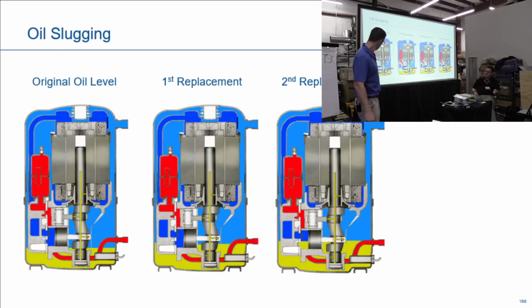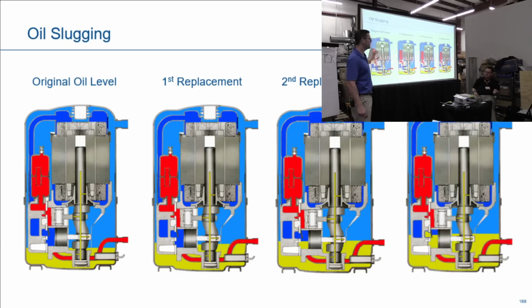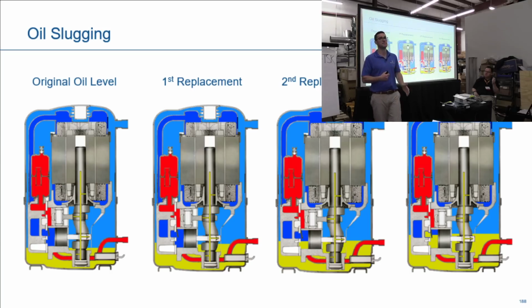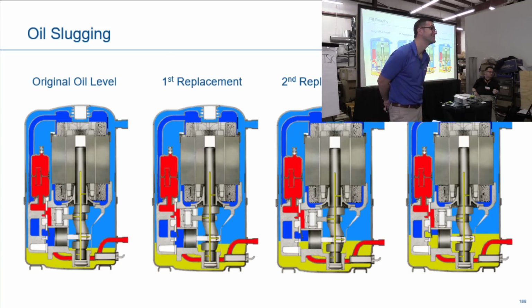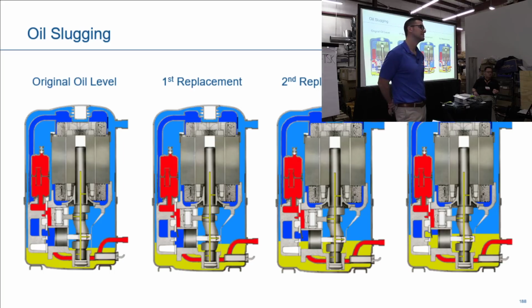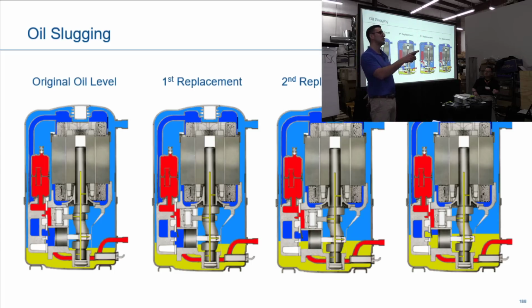Right? So look, here's where our pistons, and this is an example of a hermetic. But look, you get oil right in the piston so that, right? Question. Yeah, I was just curious, so if your compressor has that much oil in it when you pull it out, then how do you still have that much oil in the system? Because you're adding oil back into the system? Okay, that's a very good point. So if somebody's changing it here and here, where's the oil at this point? Just changing it right here.